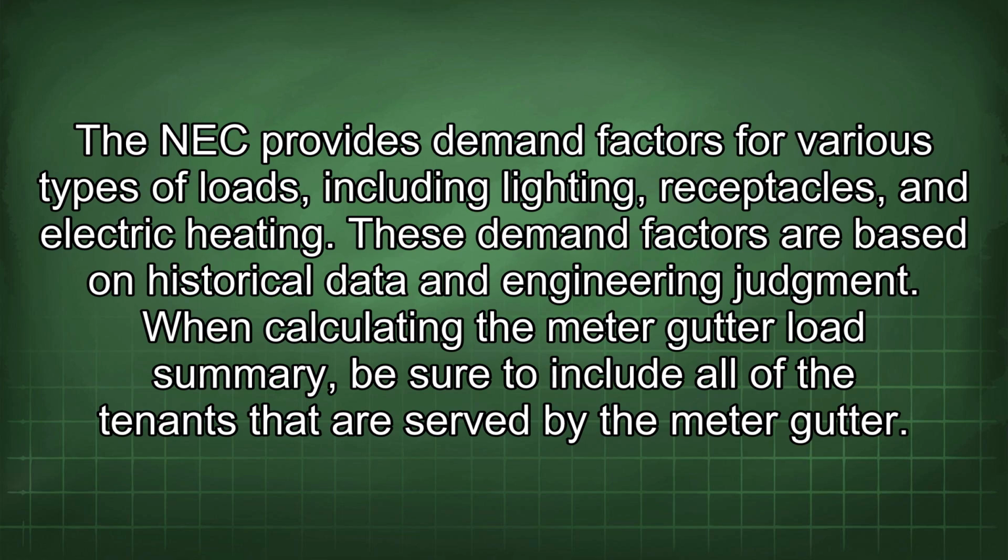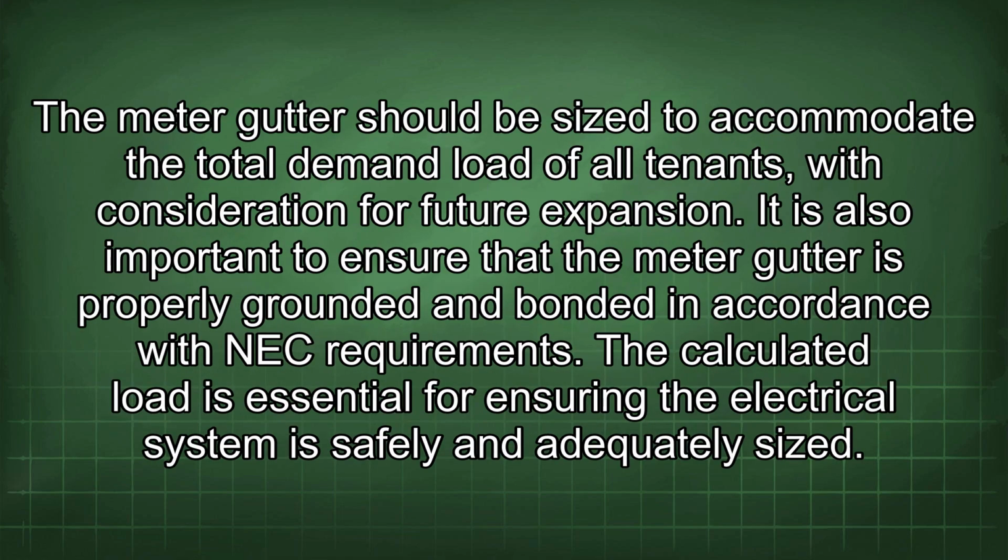When calculating the meter gutter load summary, be sure to include all of the tenants that are served by the meter gutter. The meter gutter should be sized to accommodate the total demand load of all tenants, with consideration for future expansion. It is also important to ensure that the meter gutter is properly grounded and bonded in accordance with NEC requirements. The calculated load is essential for ensuring the electrical system is safely and adequately sized.